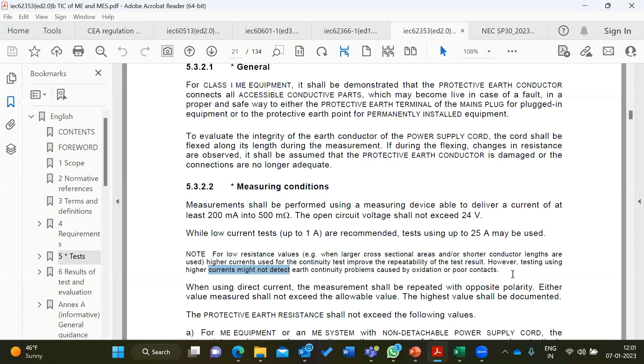See, if you look at a continuity resistance meter of 1 ampere or 25 ampere, these are not small multimeters. These are called high current micro ohmmeters. Micro ohmmeter means it can measure very, very low resistance connections. Now note, for low resistance values, when a large cross-sectional area and shorter conductor length are used, higher currents used for continuity test improve the repeatability of the test result. However, testing using higher currents might not detect earth continuity problems caused by oxidation or poor contacts. So basically, this particular standard is probably one of several standards.